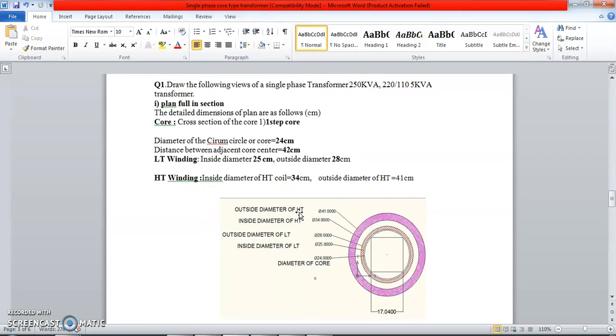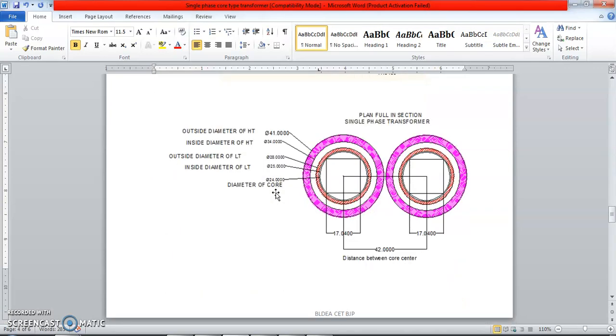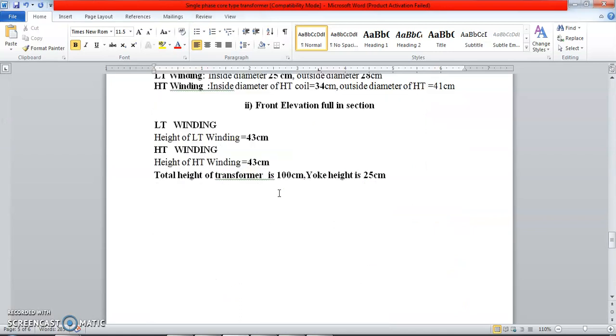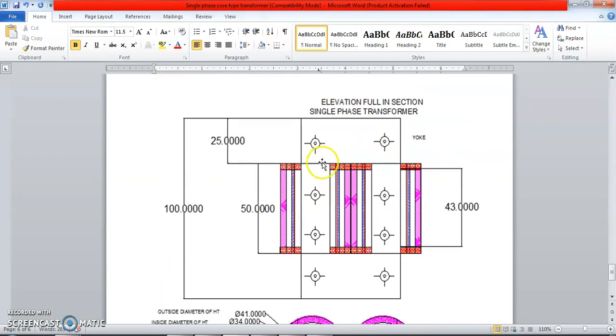In elevation, we look at the height of the transformer. The total height of the transformer is 100 centimeters and the yoke height is 25 centimeters. So to draw the elevation section you need to know: total height, yoke height, and core dimensions. Total height is 100 centimeters, yoke height is 25 — 25 above and 25 below — so the remaining core height left in the middle is 50 centimeters.